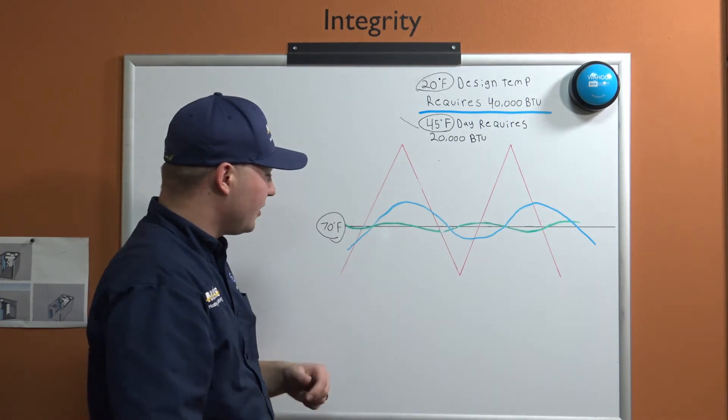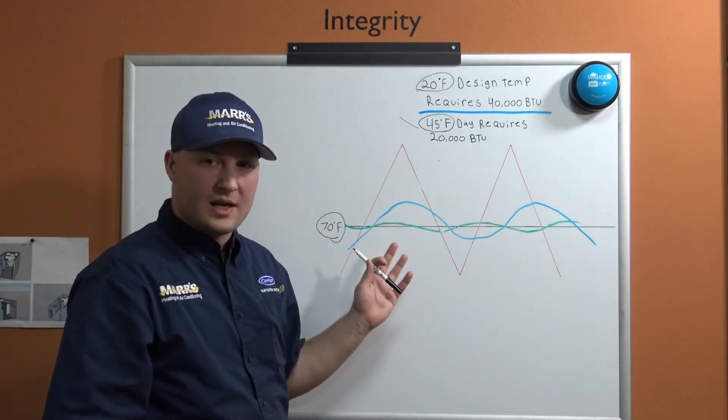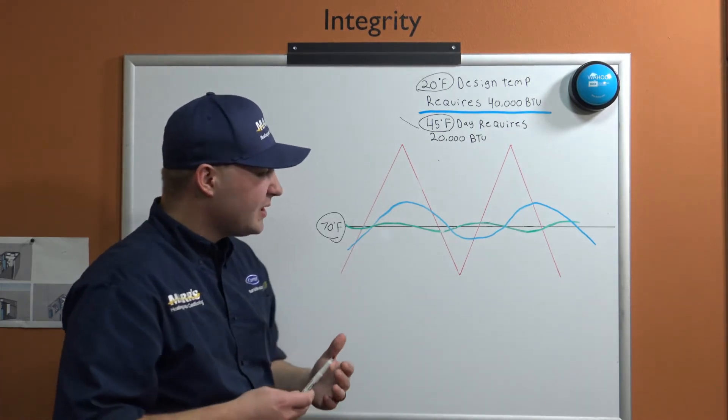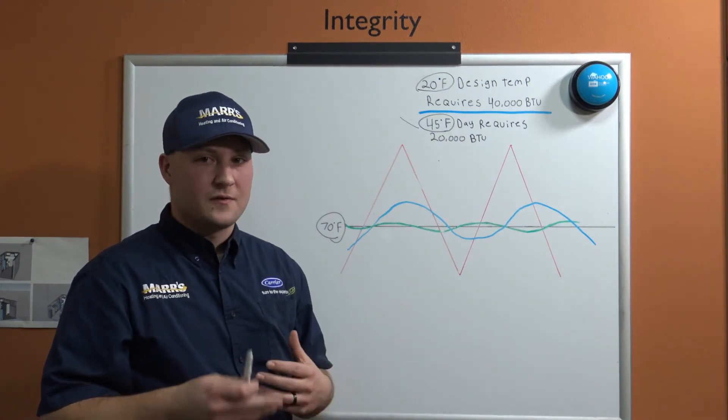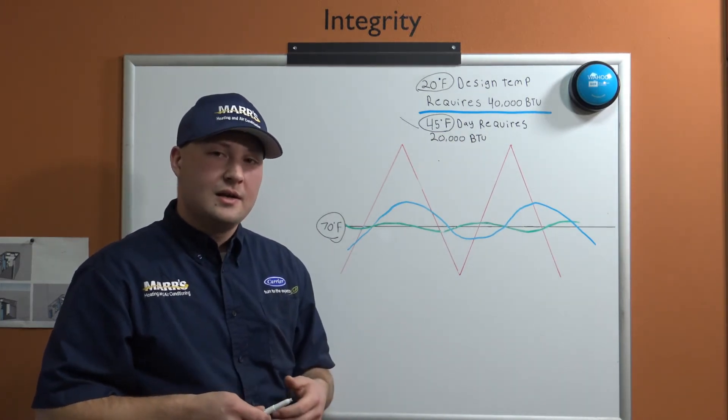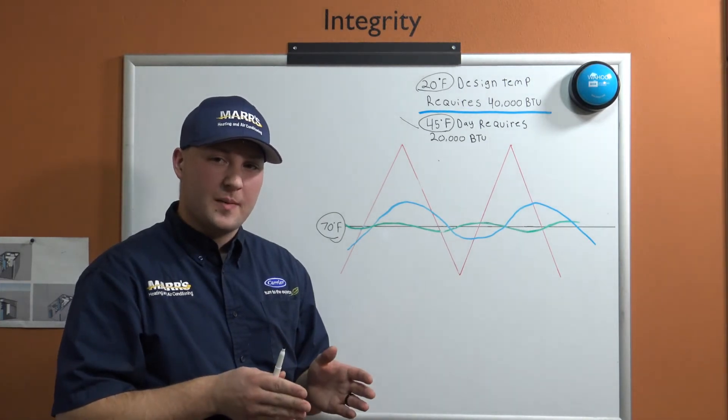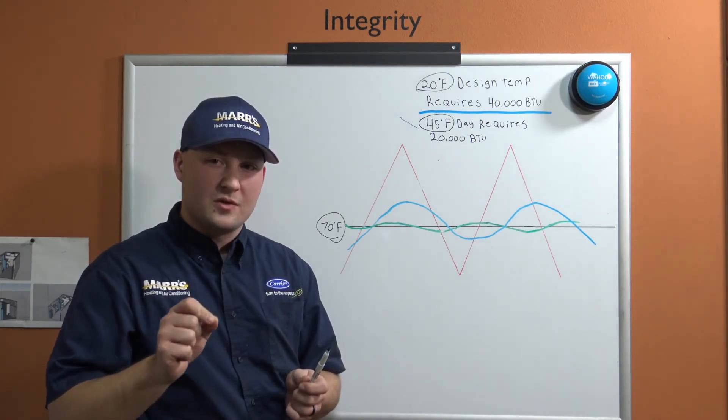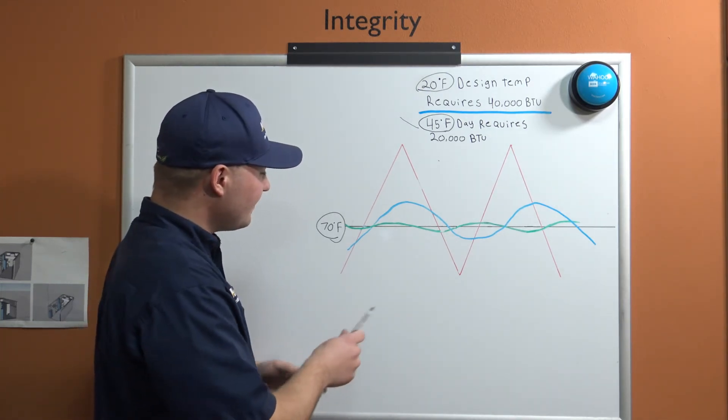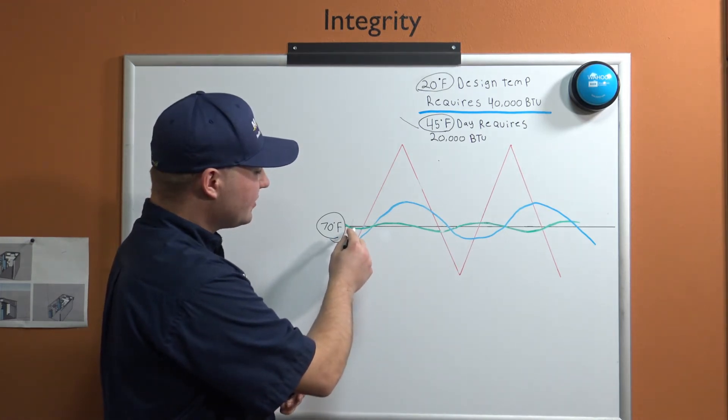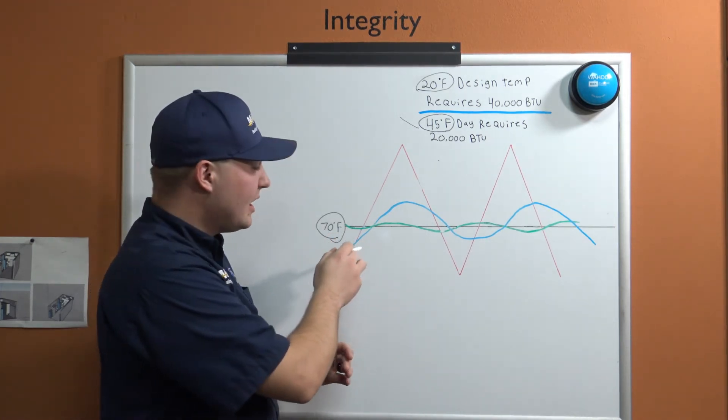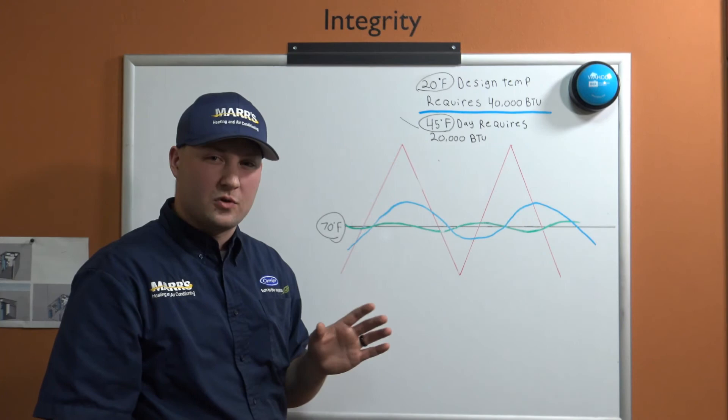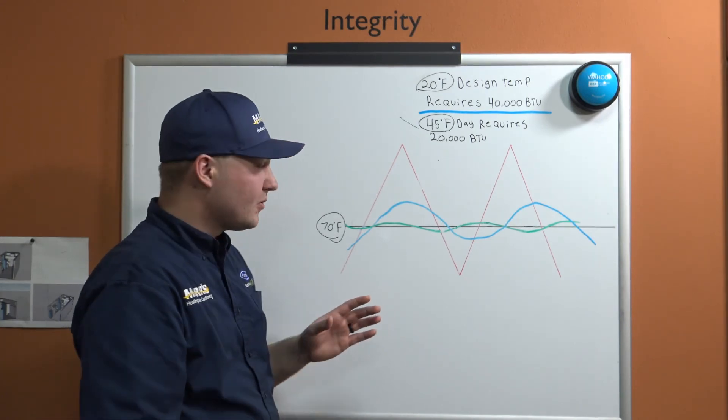With that, we'll go to our green line here, which is indicating our variable speed or variable capacity equipment. Variable speed equipment typically—and again, this differs based on equipment type, brand, etc.—typically you're going to have anywhere between 40% capacity and 100% capacity in tiny increments in between those numbers. What this is doing is our thermostat is communicating with our equipment, and we're able to ride really close to this 70 degree line, maybe even within half a degree on either side.